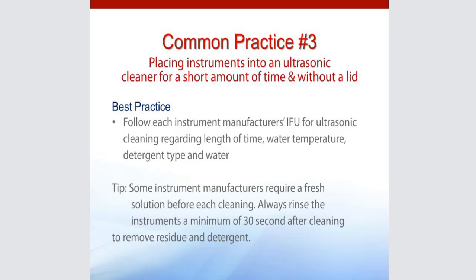There are different schools of thought about how frequently the ultrasonic solution needs to be changed. What I'm seeing more often now with the ultrasonic manufacturers is they're saying twice a day, minimum absolutely once a day. You also want to make sure that you're cleaning the tank itself, the interior of the tank, after you've emptied out the other solution. Be careful not to use any type of sprays in that tank, because you may have some chemicals left over that would react with the enzymatic detergent for the ultrasonic, so don't mix and match your chemicals.